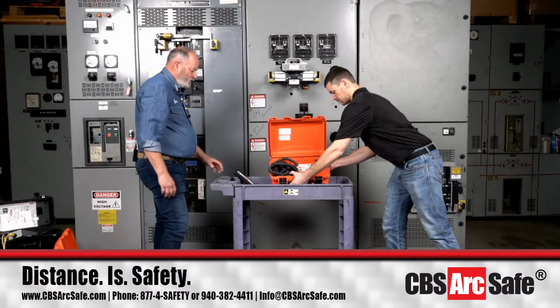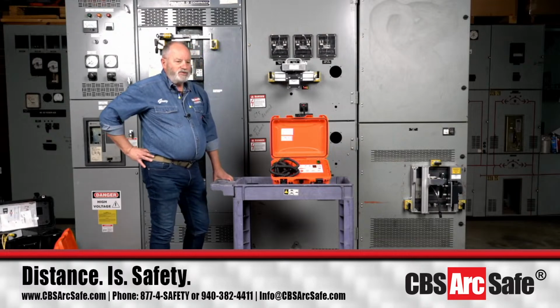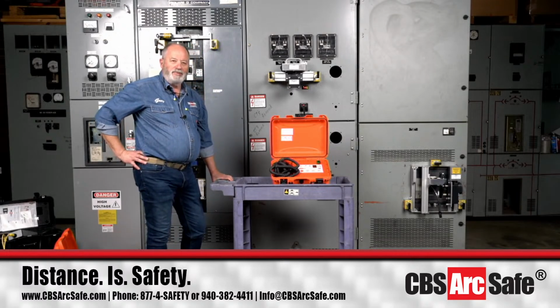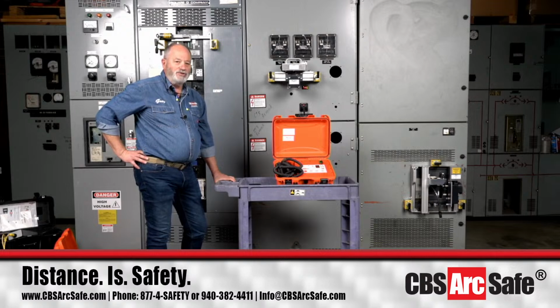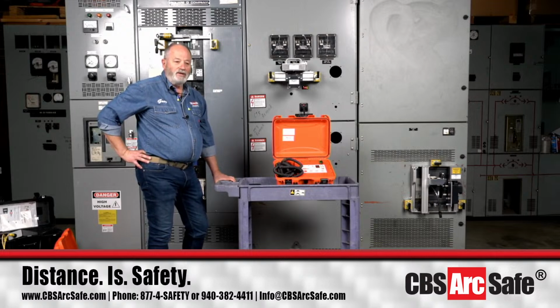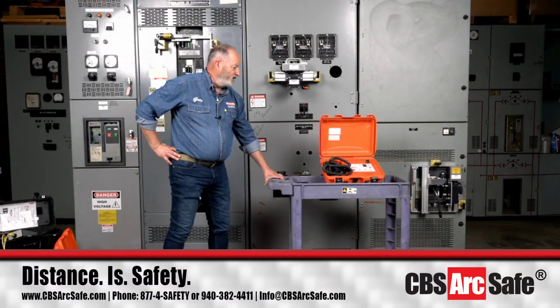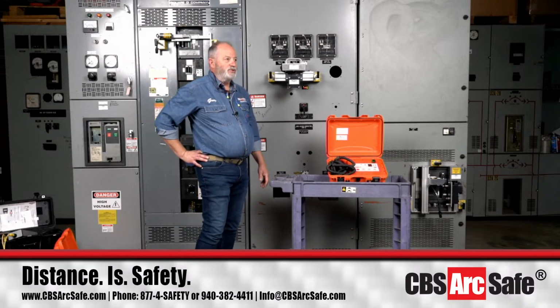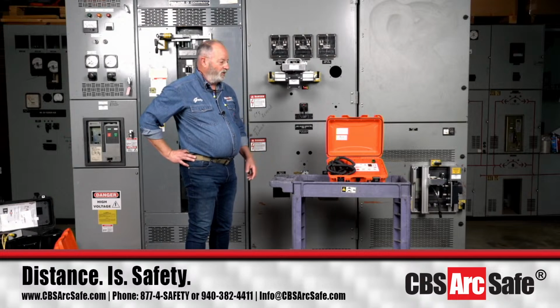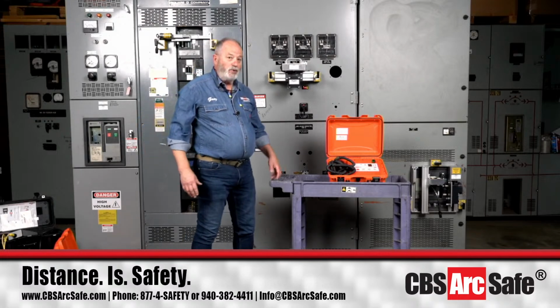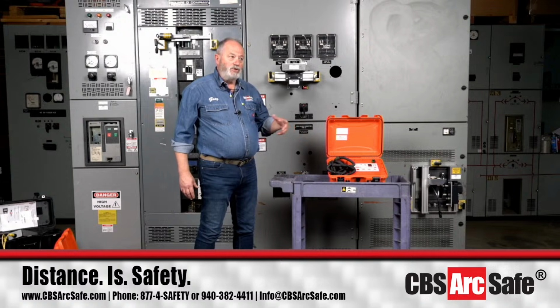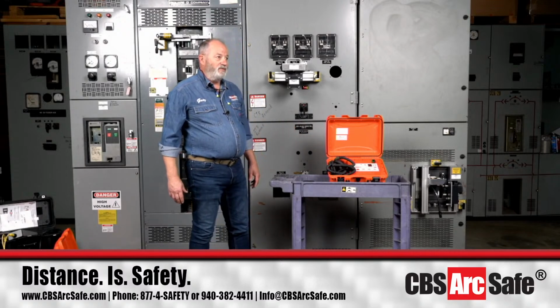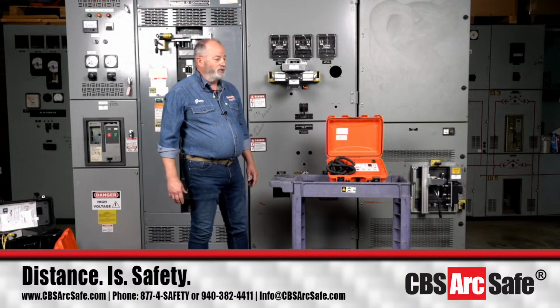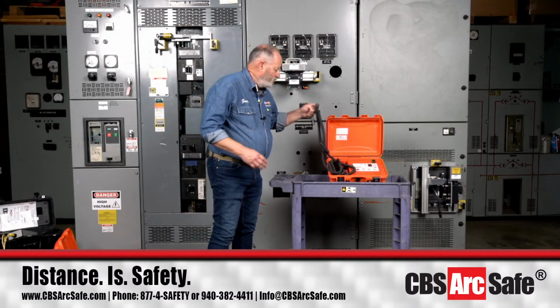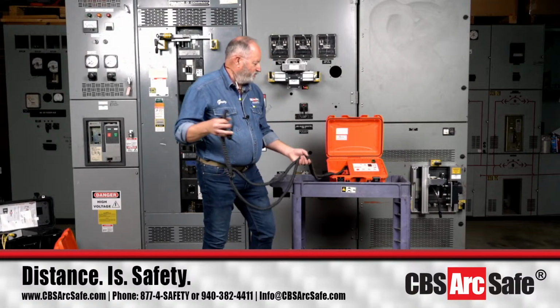One thing to note, we've seen Masterpact breakers down in Mexico, which surprised me because normally we'd say it takes 7 strokes to charge the breaker. But I ran into some down there last month where it was 6 strokes. So it's not going to damage the breaker if I keep pumping the arm up and down, but it was surprising that it was less than what we'd seen before. We are always learning from you, the customer, and what you have in your facilities. We've got 15-plus years of learning, and we learn new stuff every day. So we share our information to help you safely operate this equipment.